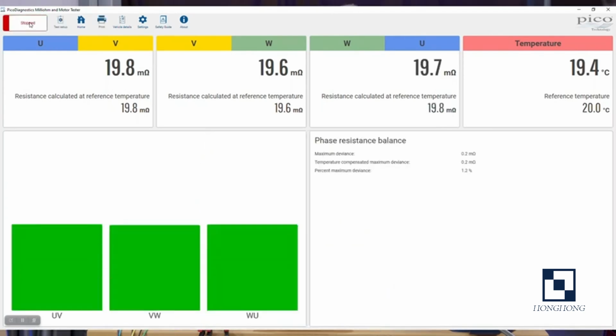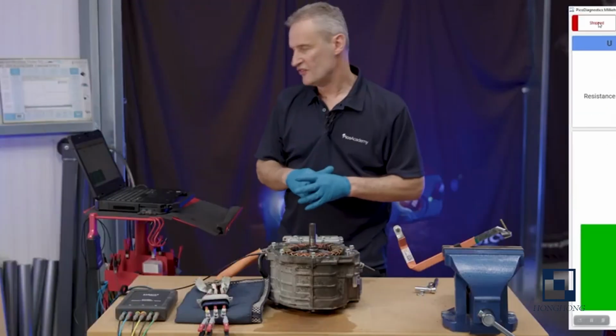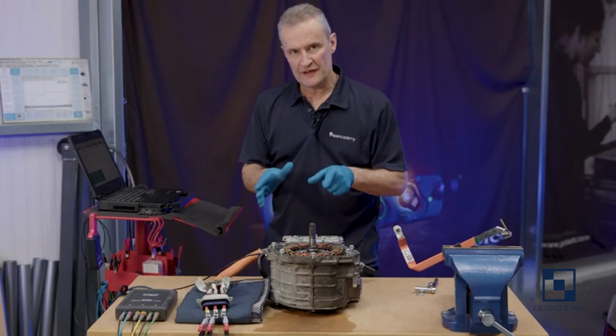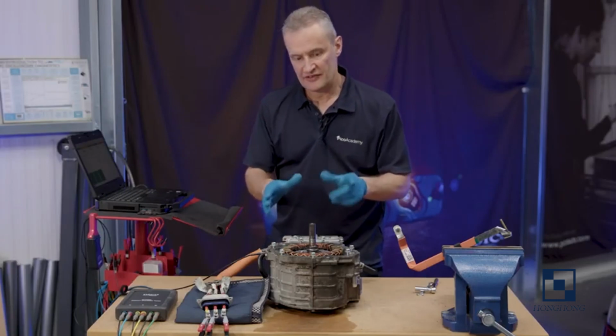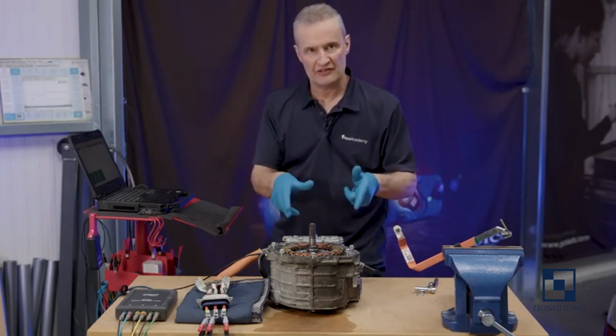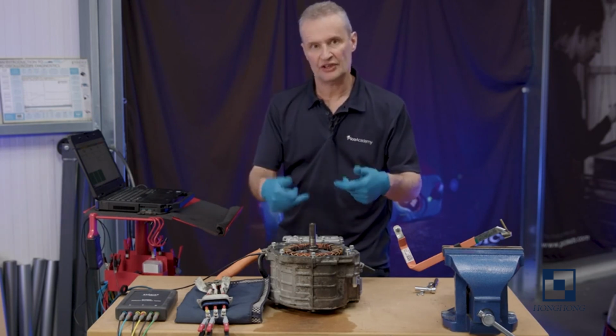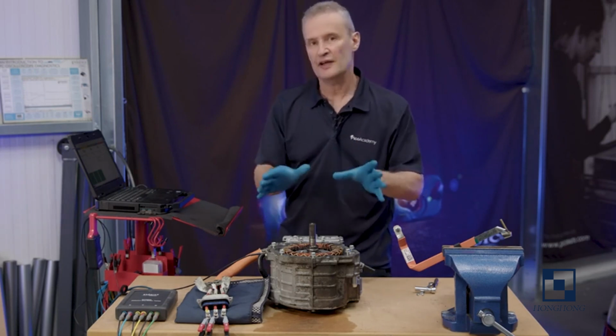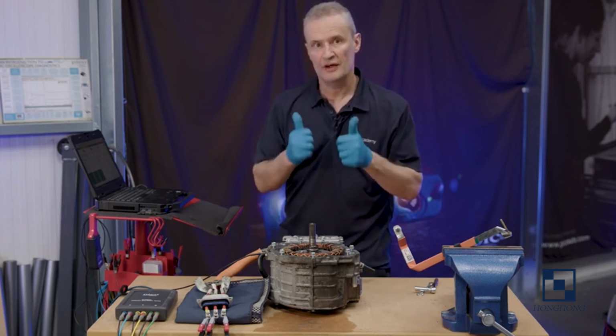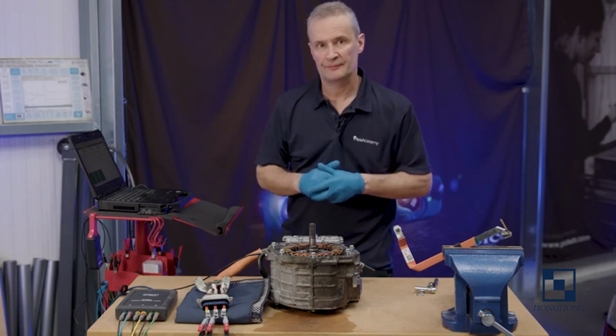So the bar graph there informs us that this is a good motor. Balance-wise, it's fine. Another worthy check, especially if this is a second-hand device, is to now do an insulation test. Of course we use high voltage to measure for a short to earth, but certainly from a phase balance point of view, this is a good motor.